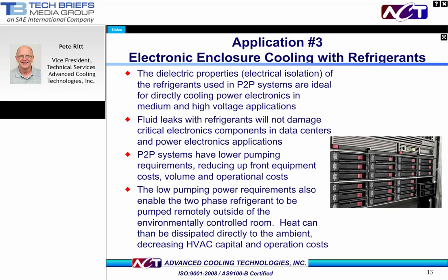We have already shown that many P2P applications use refrigerants. In addition, the lower required pumping power of P2P systems can reduce upfront costs of implementing these systems. That lower pumping power also enables the waste heat to be cost-effectively pumped to external locations to be dissipated. This can provide HVAC and facility savings, as the cost to maintain tight temperature limits within these environmentally controlled rooms is reduced.